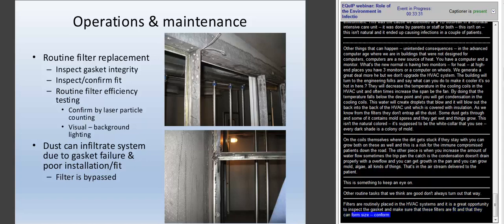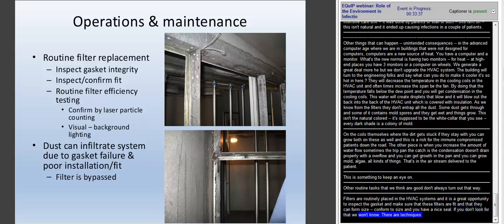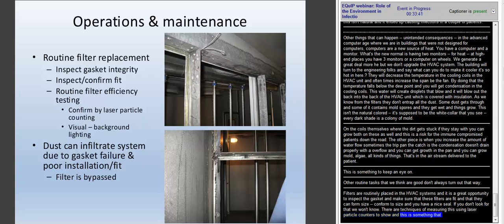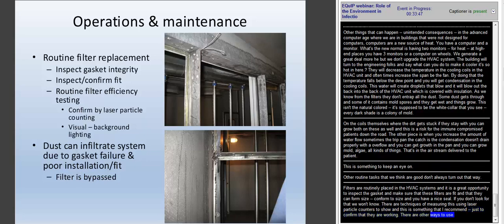So there are techniques of measuring this using laser particle counters to show, and something that I recommend is done every time you do that, just to confirm that they're working. But there are other ways of using high-intensity visual background lighting and going on the other side and looking to see if light leaks through. And if you see that, you know you're getting filter bypass.